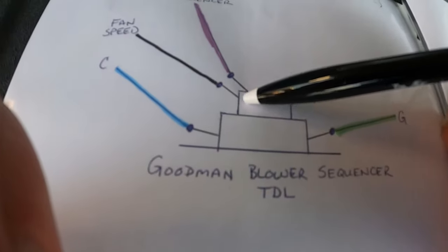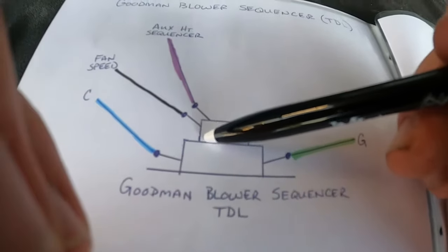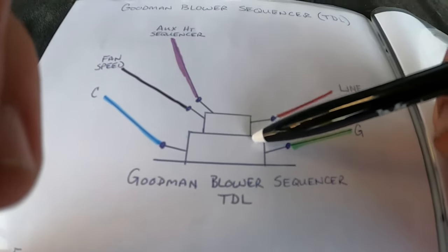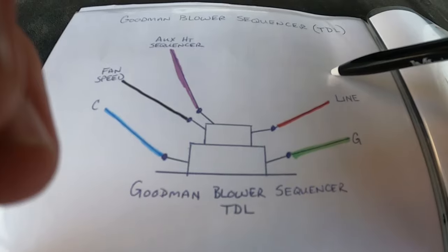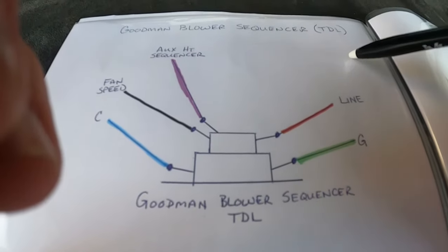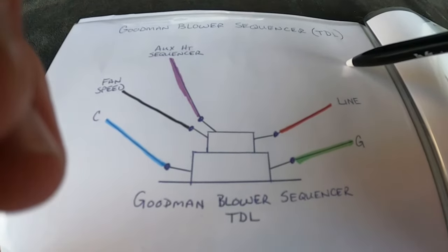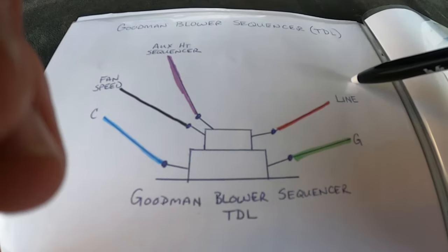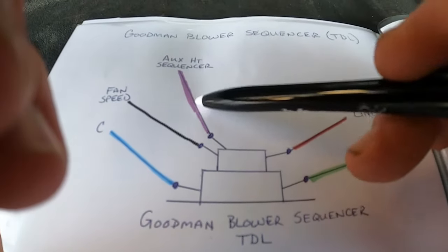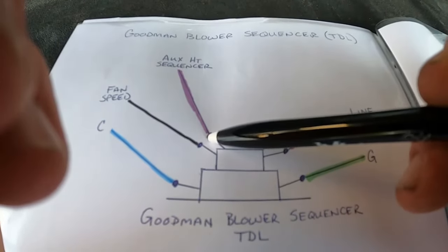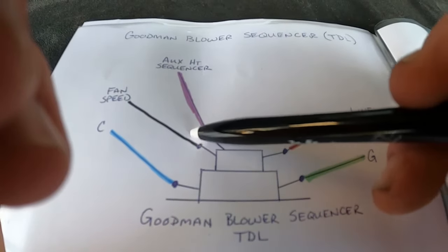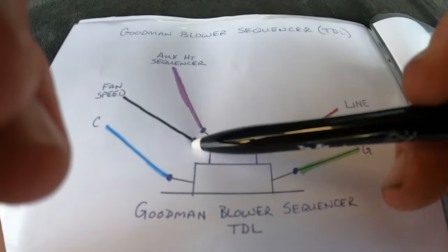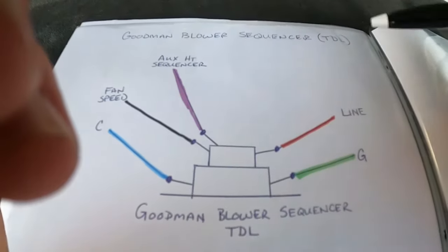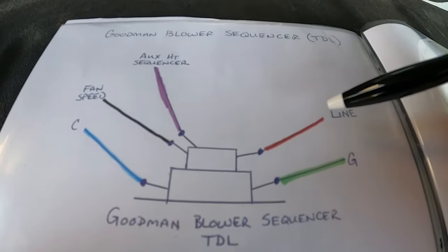That particular sequencer, this is normally closed. So in this situation, with these Goodman and Amanas, if your heat sequencer gets energized, it closes. When it closes, it's going to have a purple wire that comes off and back feeds a leg of power here. It's going to energize this normally closed switch for your blower speed, and your blower is going to run when the heat strips come on.